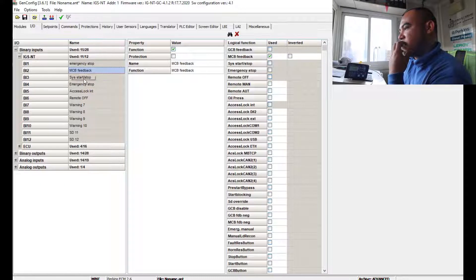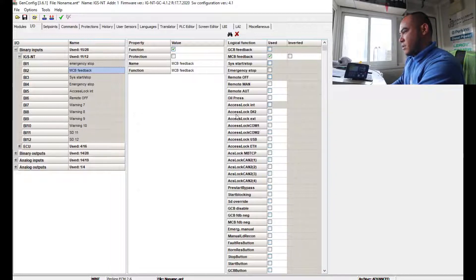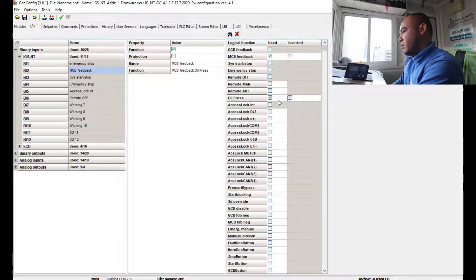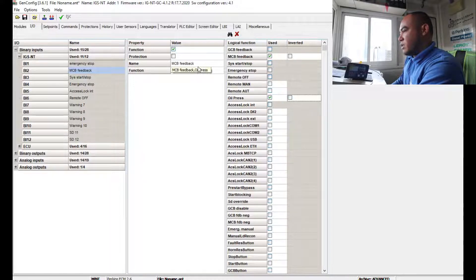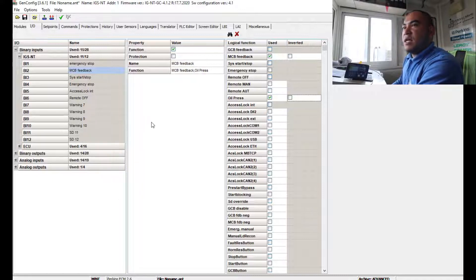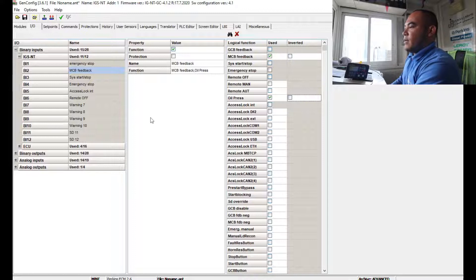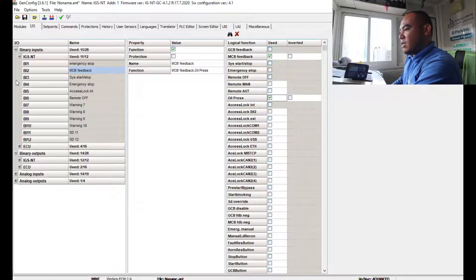For other binary inputs such as B2, you can configure them as needed — for example, oil pressure. Click the input, select the function you need, and update the name field. The name displayed on the module will only change if you update it here; otherwise it will remain as the default, like 'MCB Feedback'. You can configure B1, B2, B3 and so on in the same way. When done, close this section to move on to binary outputs.